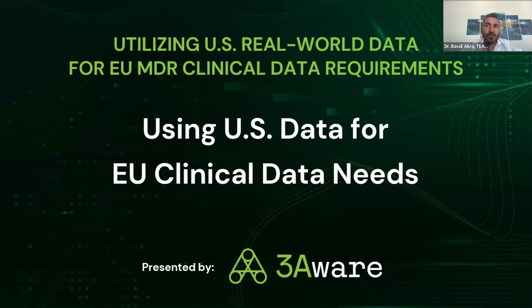You would do the same thing if you are applying equivalency, because the European legislation, including the guidance MDCG 2020-5 regarding equivalency, allows manufacturers of class 2A non-implantable devices to compare their devices, on an equivalency approach, to a non-European approved device. And if you compare to a non-European approved device and use its data, you would need at least a confirmation before the recertification, which shows that applying that device in Europe for that intended purpose, for that indication, will lead to the same kind of data, the same kind of output, or even better.